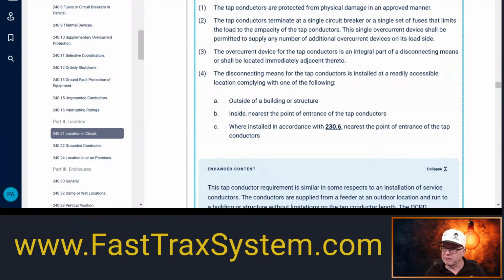Okay, so that disconnecting means is to be either on the outside of the building or structure. Okay, so outside the disconnect, and of course, then you can be immediately adjacent, could be immediately on the other side of the wall. We could argue that. It says inside, nearest the point of entrance of the tap conductors. So the moment that those tap conductors turn, say with an LB, into the actual building, boom, they're going to go right into a disconnecting means. Maybe it's the panel with the main breaker, or maybe it's a separate disconnecting means, as you saw. That's your choice.